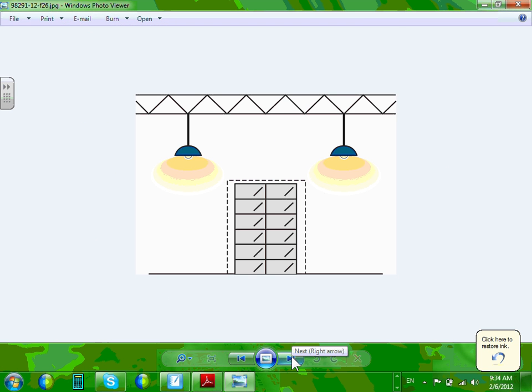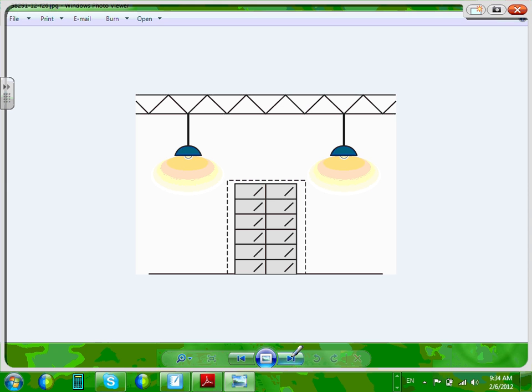A few other things left, guys, is light. In the mechanical equipment, in the electrical closets, and in the electrical equipment, you have to have a light. Anybody know why we have to have a light? We're working on energized equipment, so for Pete's sake, you have to have a light. They want you to place your light close to the switchgear without entering the dedicated space or working space. You can't enter dedicated space.